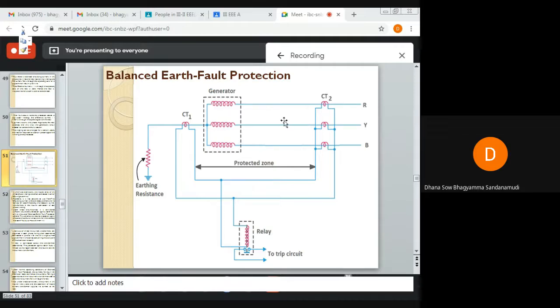You can see in this image, on the other side of the alternator windings, on each phase, the primaries of the CTs are connected and their secondaries are connected in parallel. So for the R, Y, B phases, the primaries of the CTs are connected in series to one end of the alternator windings, and the secondaries of the CTs are connected in parallel. Similarly, there is a single current transformer on the conductor joining the star point of these three alternator windings to the earth.